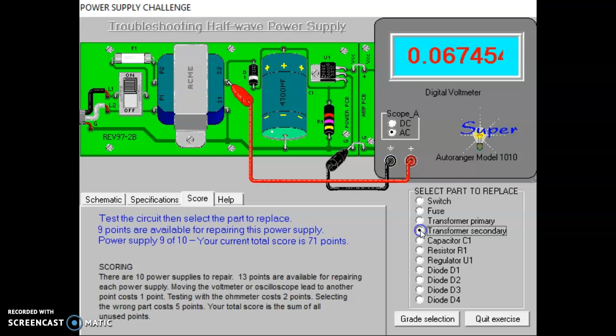Looking at this one, we look at our AC input, AC output. Again, let's double check this transformer. We'll look at the secondary side. I suppose I should show you how to look at the primary. In this case, it's the secondary that's bad, it's got an open infinite resistance, so the secondary is the bad side. We'll turn that off. Transformer secondary is what's bad. Grade the selection, we're good to go.